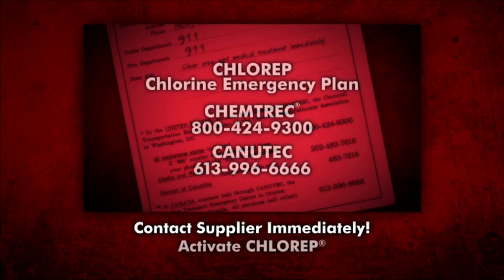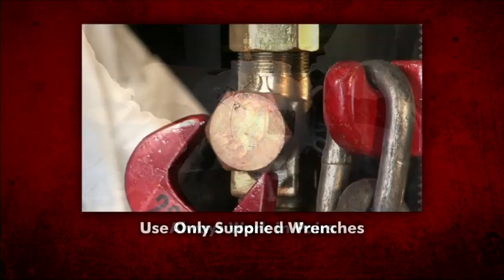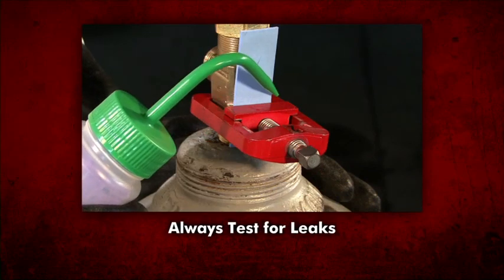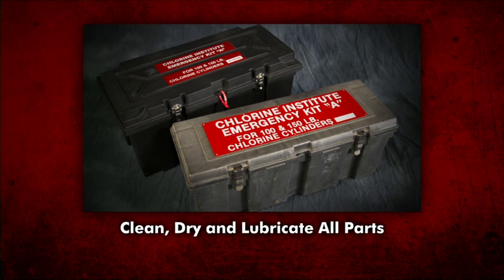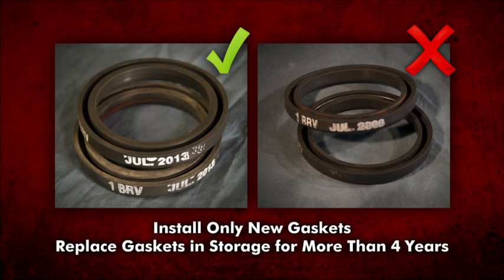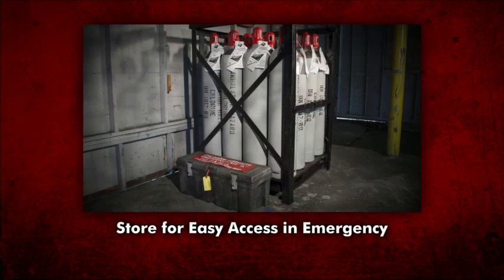If further assistance is needed, activate CHLOREP through CHEMTREC in the United States or Canutec in Canada. Always work calmly, in pairs, and under control. Work to do it right the first time. When applying devices, use only the wrenches supplied with the kit. Always test for leaks after applying any kit device. Make arrangements with your supplier immediately to dispose of any remaining chlorine in the cylinder. Clean, dry, and lubricate all parts after each use. Install only new gaskets, and replace gaskets after four years of storage. Establish a regular routine for inspecting your kit. Store the kit where it's easily accessible in an emergency.